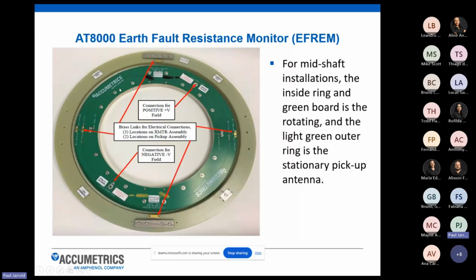So the transmitter has a trace of wire that's connected or looped around the outer diameter of the rotating transmitter. And then the pickup antenna has a wire that is machine grooved and epoxied in place on the ID of the pickup antenna. So you can get an idea of the air gap between the rotor and stator, what we would usually see. It's anywhere between maybe 15 to 20 millimeters of distance between the rotor and stator. So we're bringing data back across this air gap, which is our field resistance and field voltage.